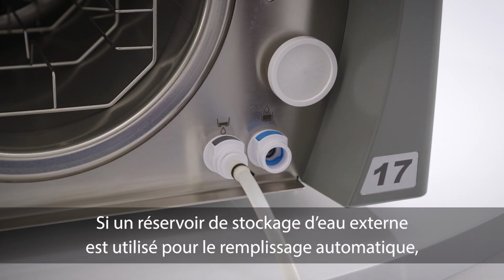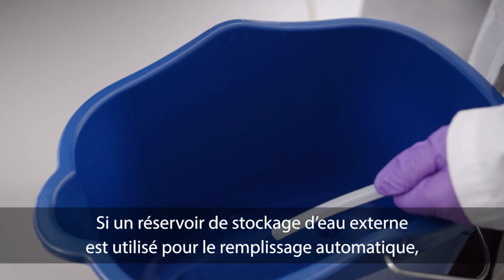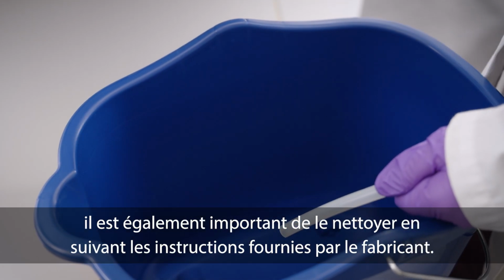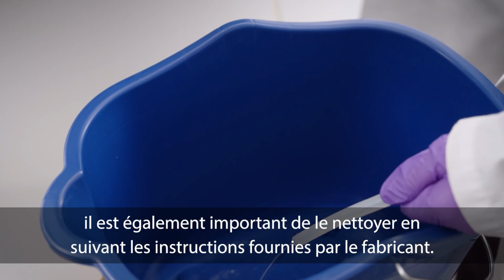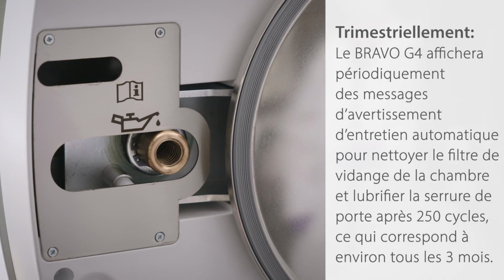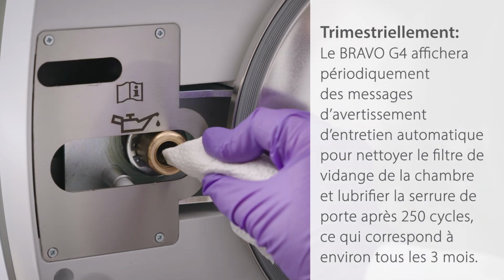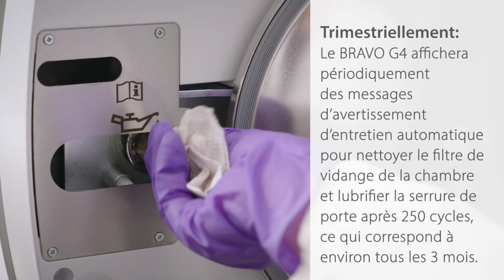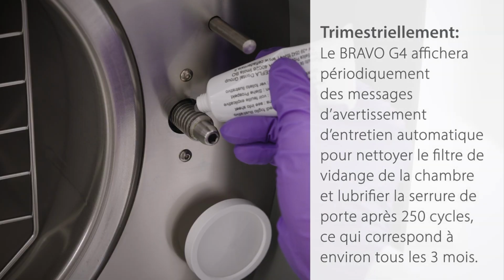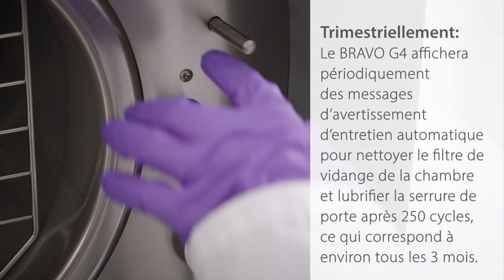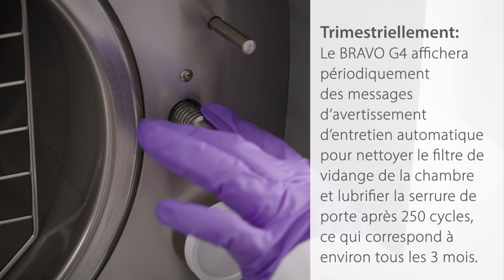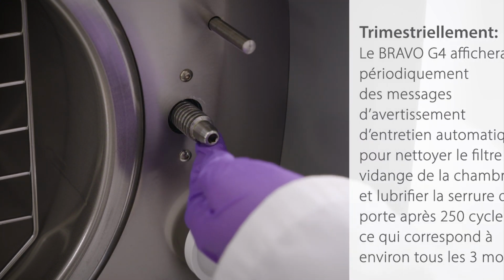If you have an external water storage tank used for automatic filling, it is also important to clean the tank, following the manufacturer's instructions. Quarterly. The Bravo G4 will periodically display automatic maintenance warning messages to clean the chamber drain filter and lubricate the door lock after 250 cycles, which is roughly every 3 months.